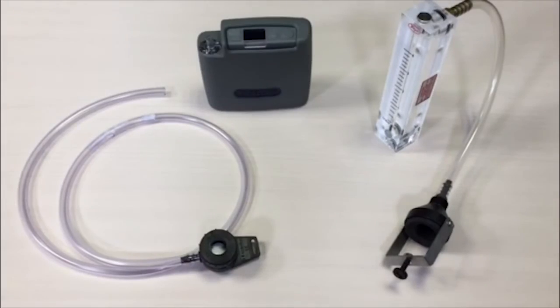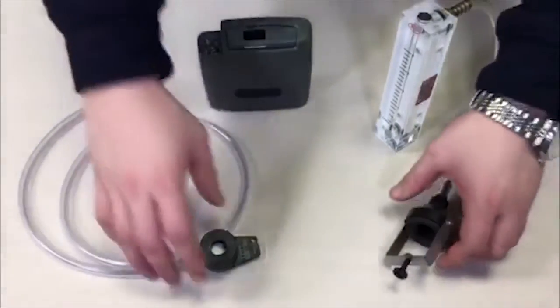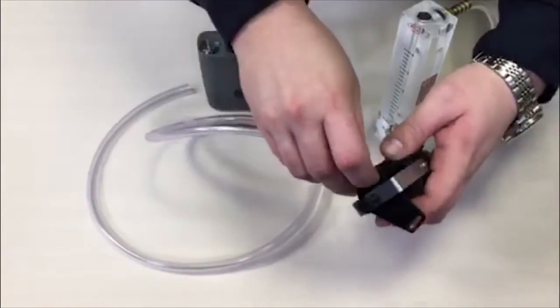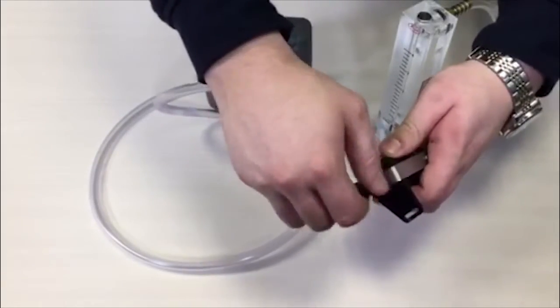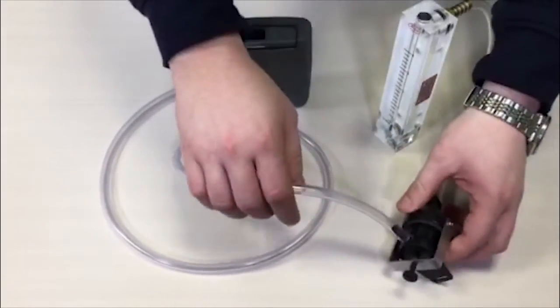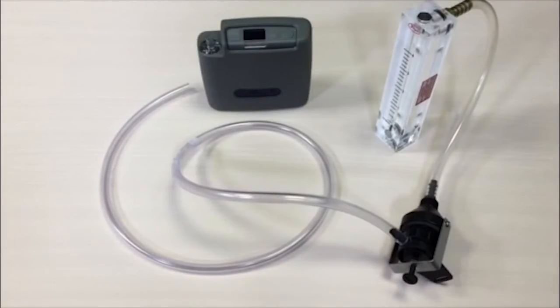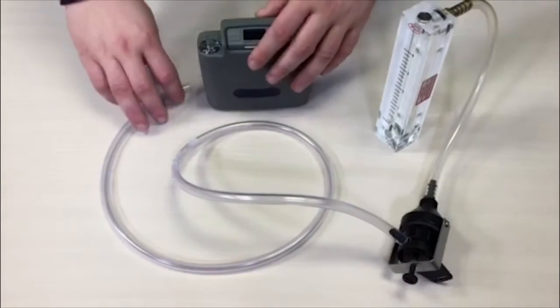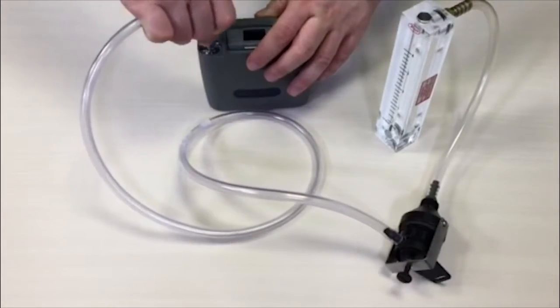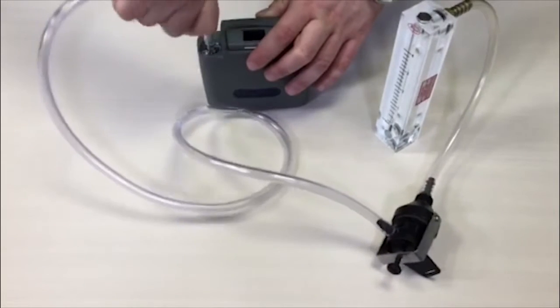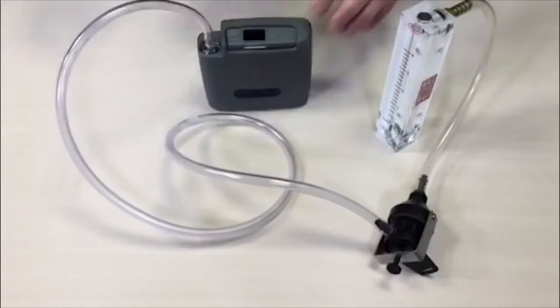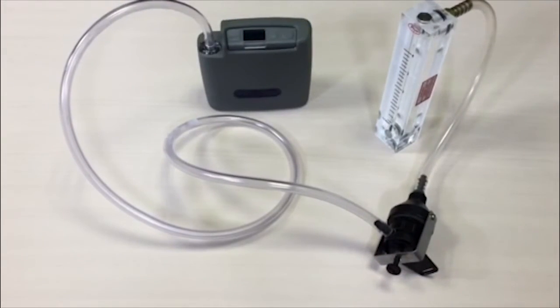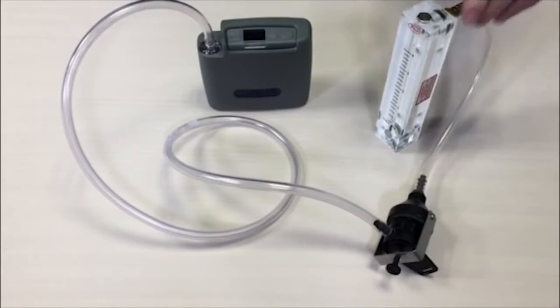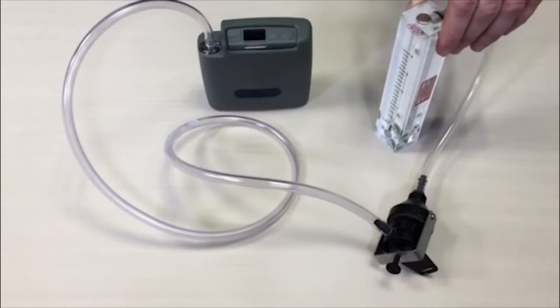To assemble the sample train ready for flow calibration, attach the sampling head to the flow meter. Then attach the sampling head to the pump. Note that the flow meter goes before the sampling head, not in between the sampling head and the pump. Ensure the connections are secure and tight to prevent leaks.